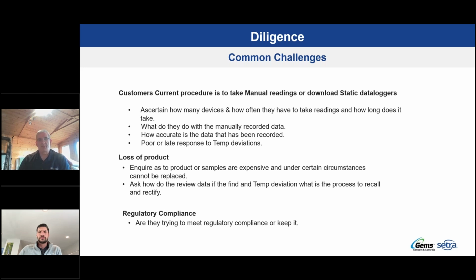With Diligence, that's negated - however you set it to take a sample, it will take the sample, store it, transmit it, and record it with a date and time stamp. If you get a deviation or an excursion, Diligence Cloud will prompt the user that there's an alarm to go fix. Without an automated platform, you're left trying to rework the data after the event, which is a lot of work and can lead to loss of product, or samples that can't even be replaced because you can't get that sample any longer.